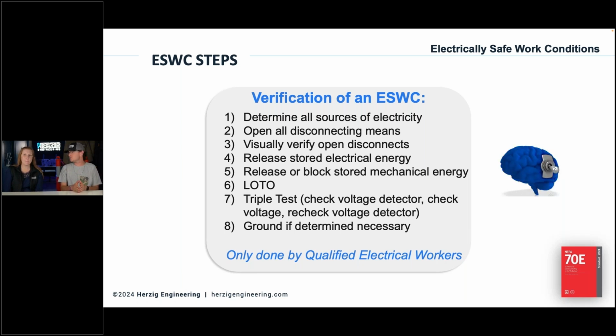That's whenever feasible, since we can't always visually verify. Number 4 is release stored electrical energy, release or block stored mechanical energy, proper lockout tagout, then triple check or triple test - live, dead, live - and number 8 is ground if determined necessary.